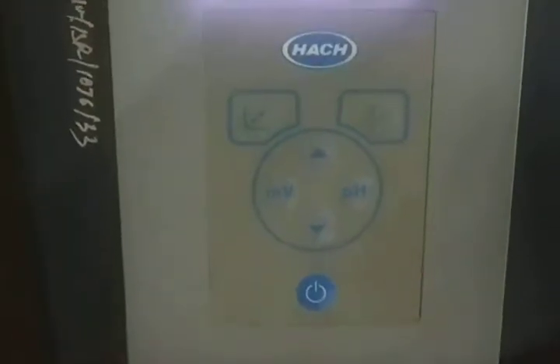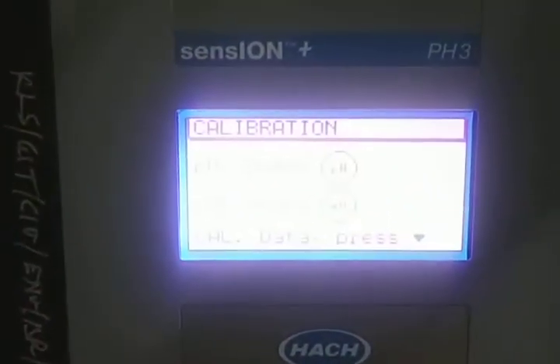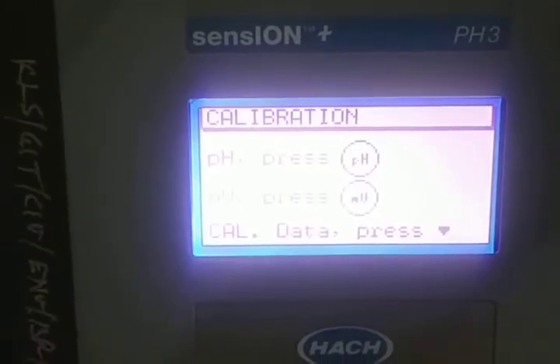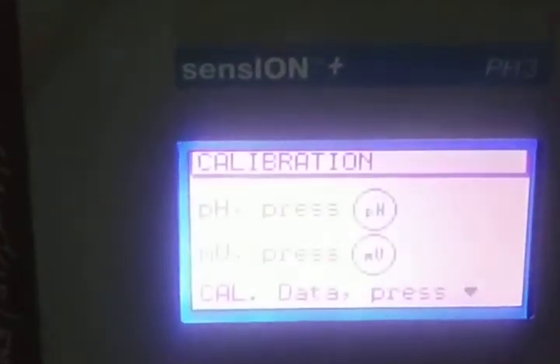Now we are going to place the buffer solution of pH value 7 and we are going to go for calibration of the instrument. So to calibrate we have got various buttons here. For calibration we will be making use of this particular button, wherein a calibration curve is being shown. So we are going to press it. We have placed the pH 7 buffer solution, and once we press the calibration button, the instrument is going to ask whether you are calibrating for pH or millivolts. So we are going to press the pH button.